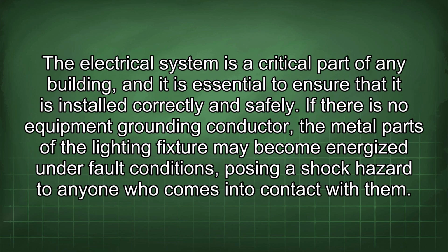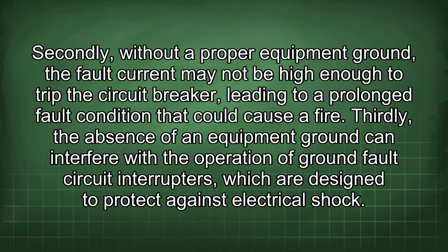The electrical system is a critical part of any building, and it is essential to ensure that it is installed correctly and safely. If there is no equipment grounding conductor, the metal parts of the lighting fixture may become energized under fault conditions, posing a shock hazard to anyone who comes into contact with them. Secondly, without a proper equipment ground, the fault current may not be high enough to trip the circuit breaker, leading to a prolonged fault condition that could cause a fire.